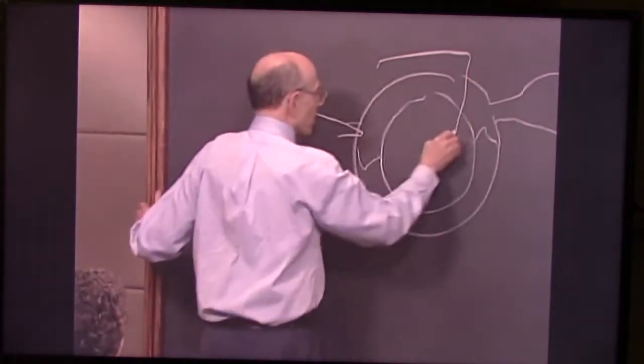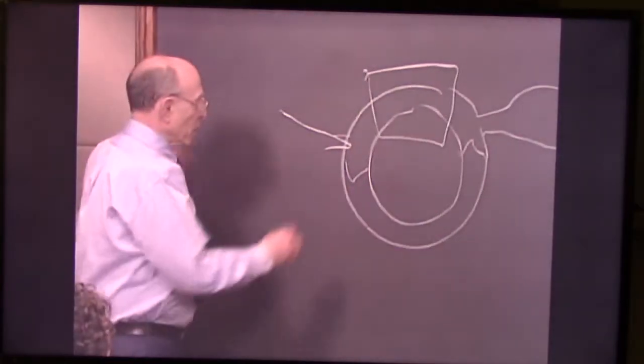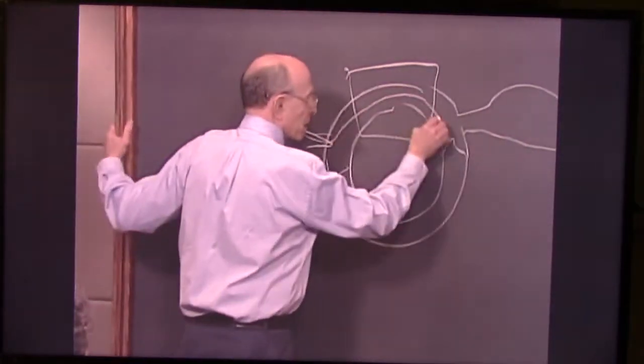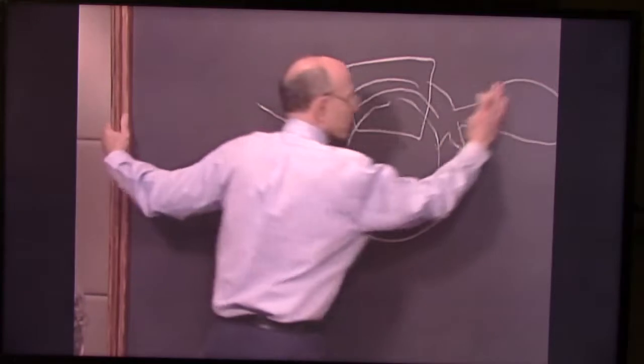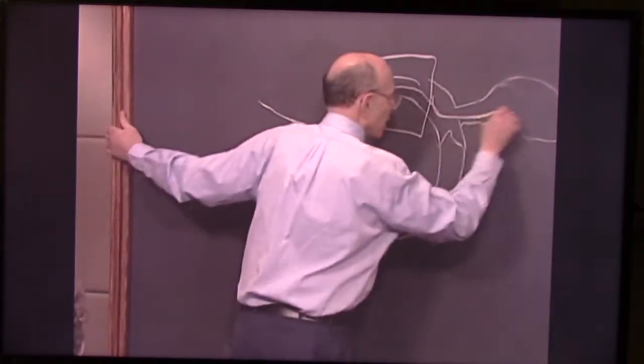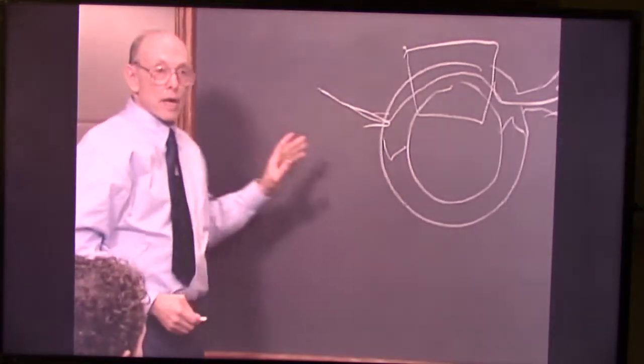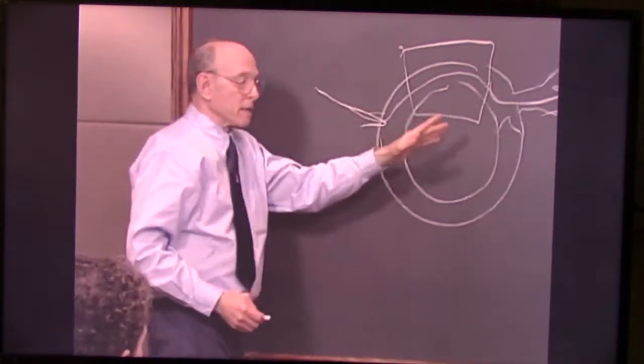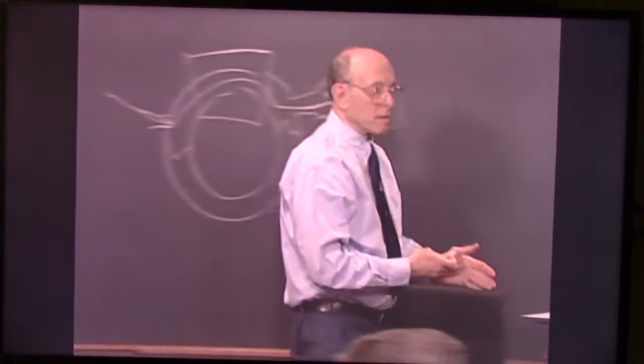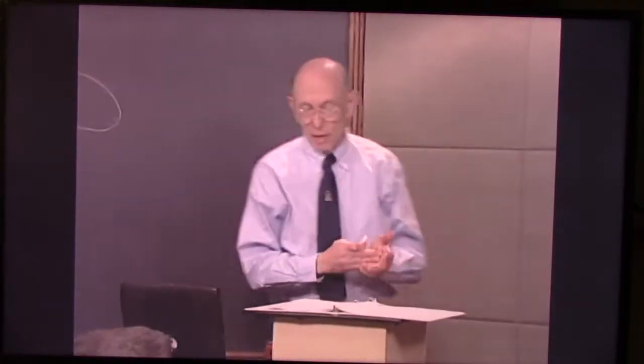And here's our absorbent here. The only way this gas can go back through here is if there's an opening here. Someone took the reservoir bag off and the gas can come out here. That's the only way you can get drying. Leave the flow on and remove the reservoir bag. Then you can get drying. And then you can get the production of carbon monoxide.